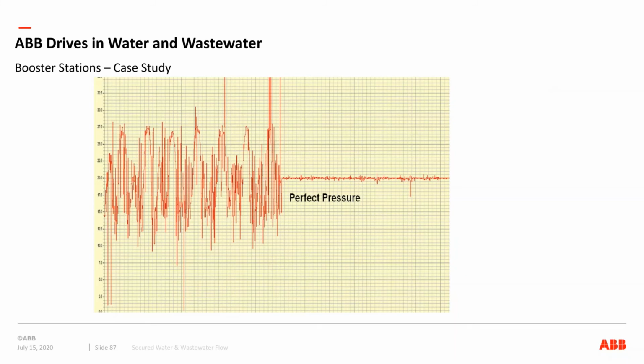Yeah, and I think you always want to try to tie the speed of the pump into something that tells it how fast to go, whether it's constant pressure, constant flow, constant level. You can use pressure transmitters. You can use flow meters. You can use DO meters, dissolved oxygen sensors. You can use nutrient detection.